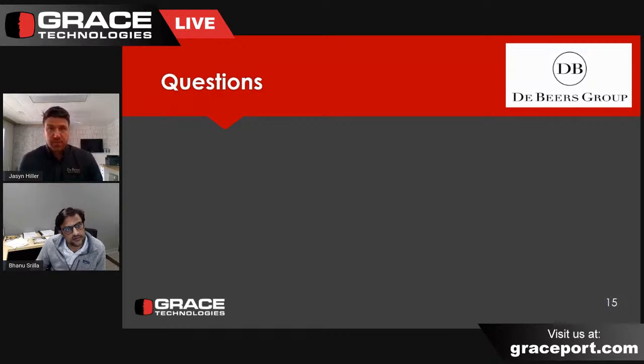Yeah, absolutely. That would be another very important procedure, lockout tagout. We have a very strict lockout tagout process. It's broken out into two categories. Category one is single point isolation with only a minimal amount of workers. Category two is used basically in the process plant, when you have to isolate multiple different systems, whether it be air, electrics, mechanical, or hydraulics, and you have multiple disciplines all working together. Then we move to what we call a lockout matrix.